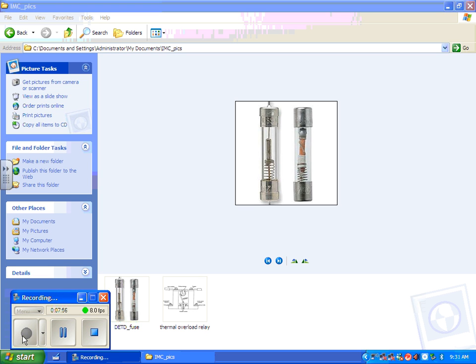Okay. Now, there are bimetallic strip devices that work more or less the same way, but slightly differently. They have two strips of metal bonded together, and they move, and they create a little movement by overheating, and they move a latch that's spring-loaded and opens up. Then there are magnetic overloads that kind of do the same thing when a certain amount of heat is created by the magnetic field, or it's not the heat, it's the magnetic field is large enough. It's assuming that amount of current is an overload. So it's kind of not really sensing the heat, which is not really what we want to do. We really want to sense the heat that's happening, because heat is the enemy of every motor.